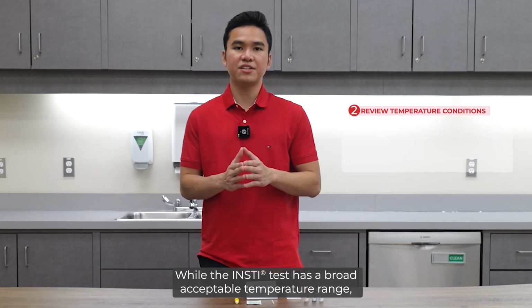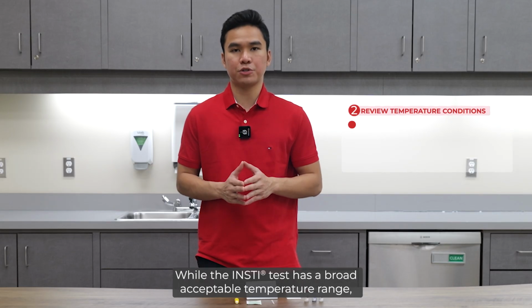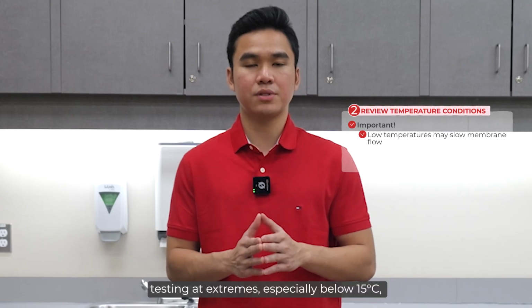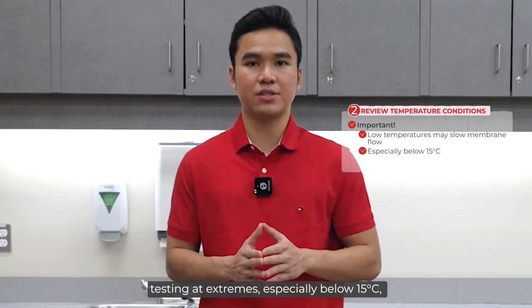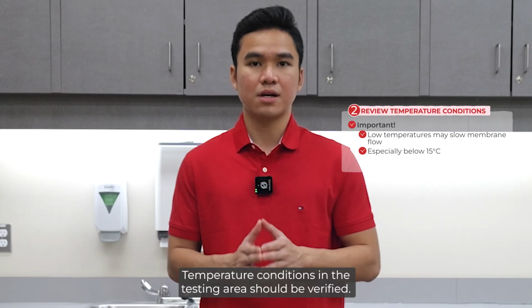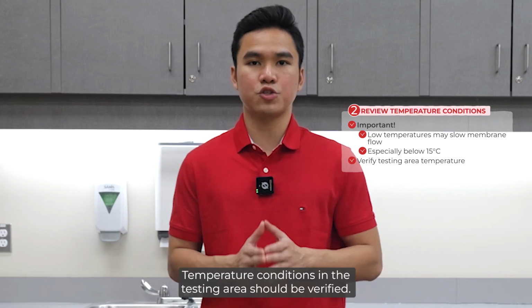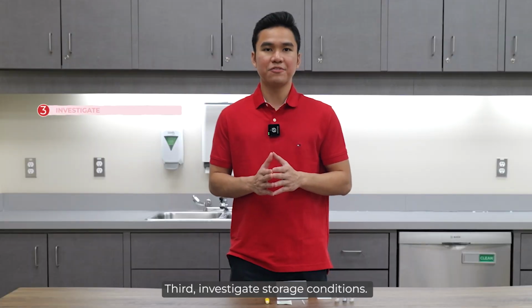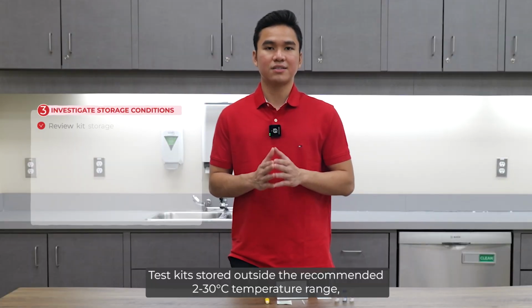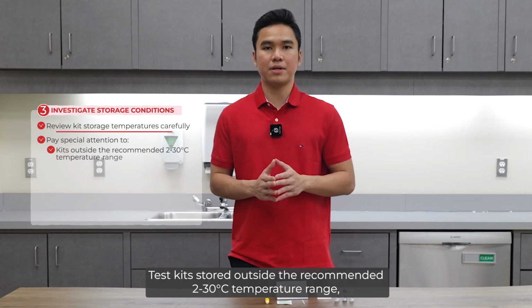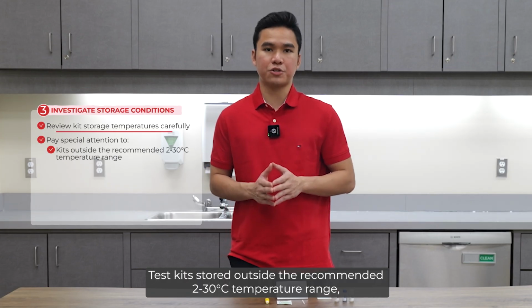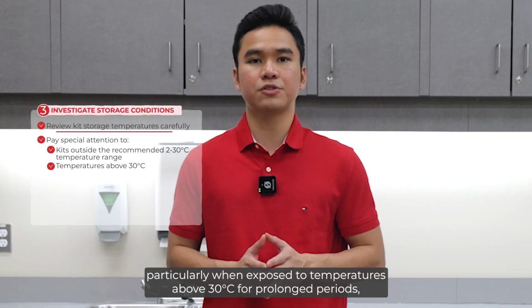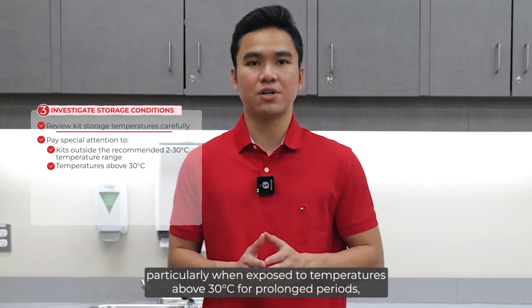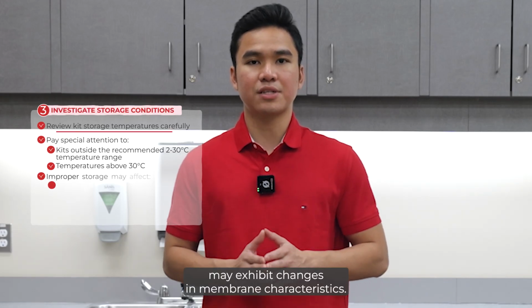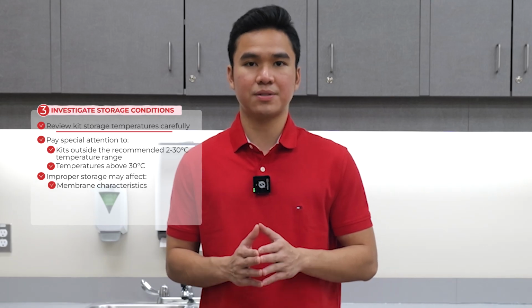Second, review temperature conditions. While the INSTI test has a broad acceptable temperature range, testing at extremes, especially below 15 degrees Celsius, may slow flow rates. Temperature conditions in the testing area should be verified. Third, investigate storage conditions. Test kits stored outside the recommended 2 to 30 degrees Celsius temperature range, particularly when exposed to temperatures above 30 degrees Celsius for prolonged periods, may exhibit changes in membrane characteristics.